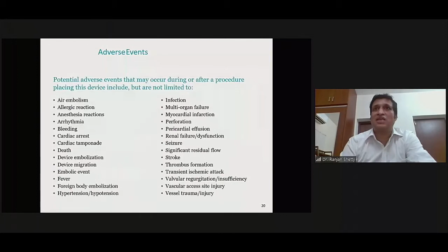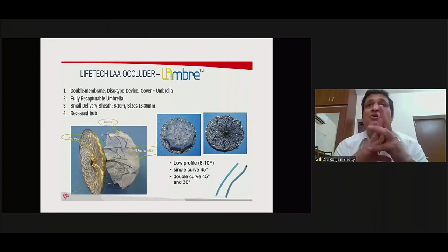So if you're using Lambre, how does the device look? The device has two parts, the body and the disc, or cover, what you call it as cover. The way Lambre differs from the ACP or Amulet is it does have one more covering, a double membrane, which is in the distal part. Hence, even with little smaller clots, you will still be able to use Lambre. It's softer. The sheath you use is 9 to 10 French. It's softer than other devices, and this is how it looks.